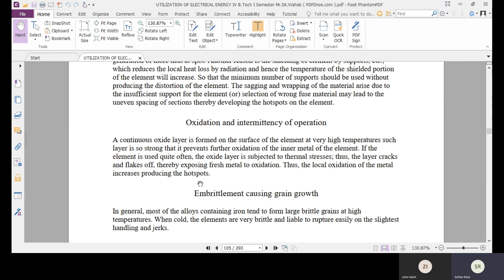So if the element is used quite often, the oxide layer is subjected to thermal stresses, and thus the layer cracks and flakes off, thereby exposing fresh metal to oxidation. Thus the local oxidation of the metal increases, producing the hot spots.